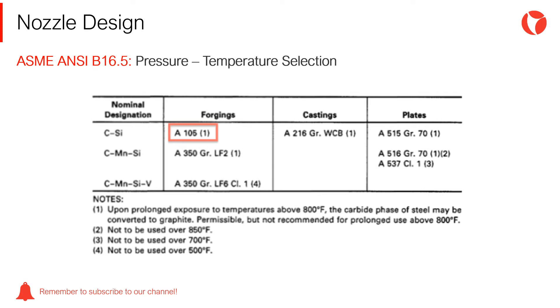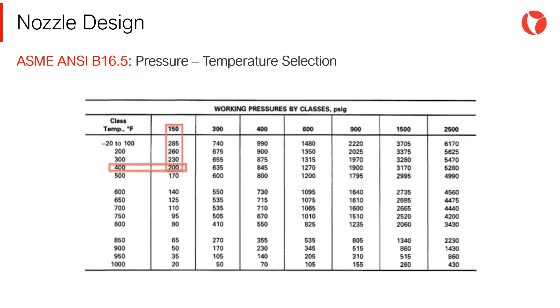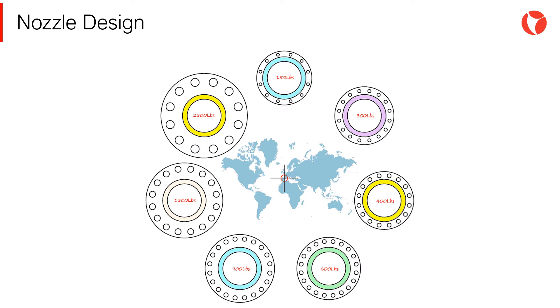Flanges up to 24 inches nominal pipe size, to be used in pressure vessels designed according to Section 8 Division 1, must be selected from the ANSI ASME B16.5 standard. When using this flange standard, the first step is to find the adequate chart for the flange material required. Then, the pressure class or rating must be determined from the pressure-temperature range corresponding to the flange material — in other words, we need to select how strong the flange should be to withstand the pressure and temperature effects.